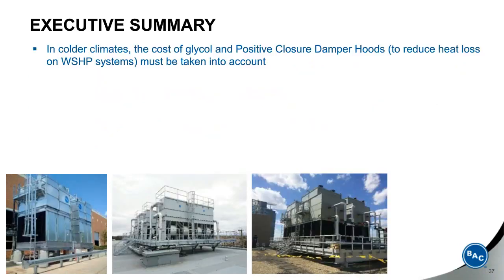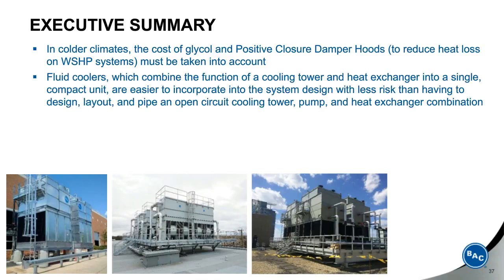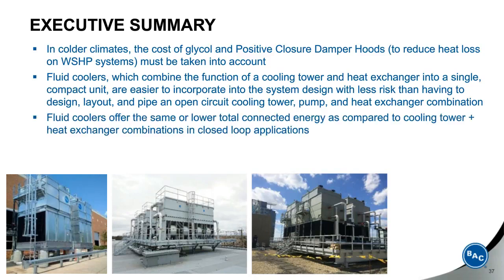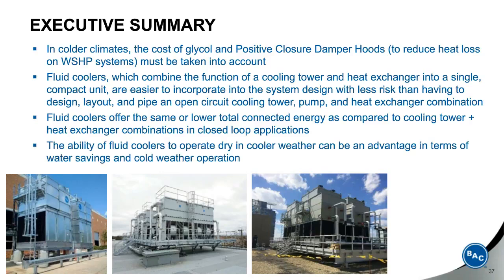In colder climates, the cost of glycol and the need for positive closure damper hoods to reduce heat loss on the water source heat pump systems must be taken into account. Fluid coolers, which combine the function of a cooling tower and heat exchanger into a single compact unit, are easier to incorporate into the system design with less risk than having to design, lay out, and pipe an open circuit cooling tower, pump, and heat exchanger combination. Fluid coolers offer the same or lower total connected energy as compared to cooling towers and heat exchanger combinations in closed-loop applications. And the ability of fluid coolers to operate dry in cooler weather can be an advantage in terms of water savings and cold weather operation.